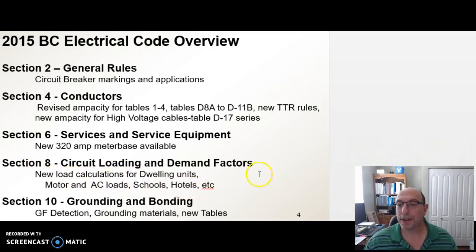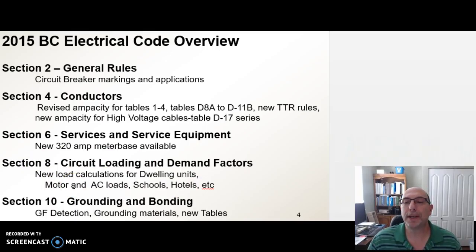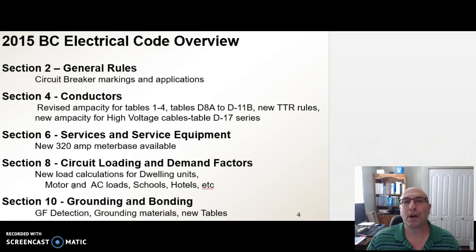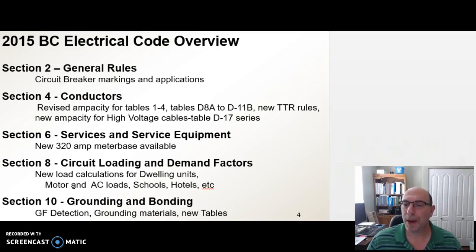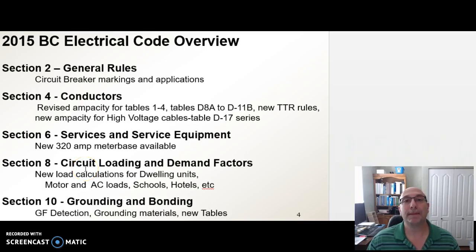Big changes in Section 8: Rule 8-200, which deals with residential, and Rule 8-202, which deals with multifamily commercial townhouses. Rule 8-202 was silent when it came to calculating the demand factors for on-demand hot water heaters, saunas, steamers, hot water steamers, or hot tubs — those were all taken at 25%. In the new code, clarifications have been made: when it comes to multifamily residencies, hot water on-demand heaters, etc., are now taken at 100%.